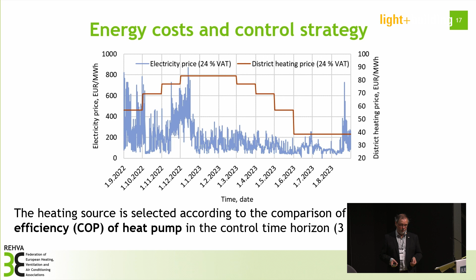Normally, with this kind of system, we have the ground source heat pump as base heating, and we only use district heating when the heat pump energy isn't enough. But in this case, when we optimize, it's based on the price signal - cost optimal means that if it's more economical to use district heating than the heat pump, we use more district heating.